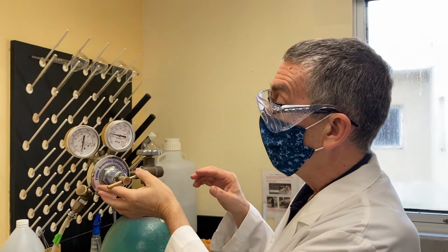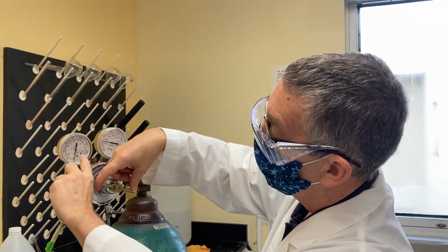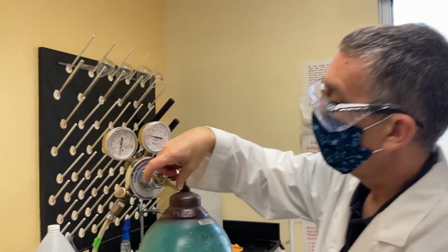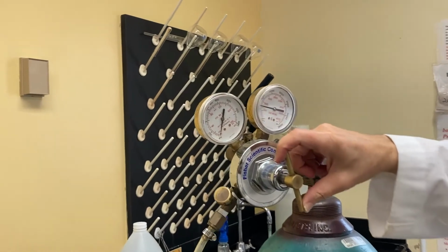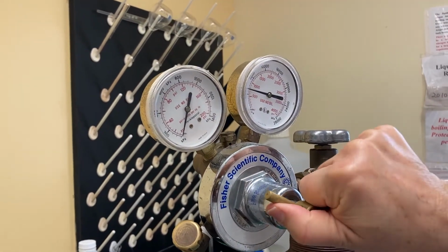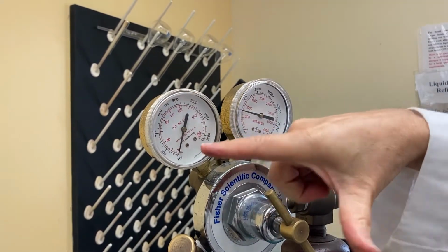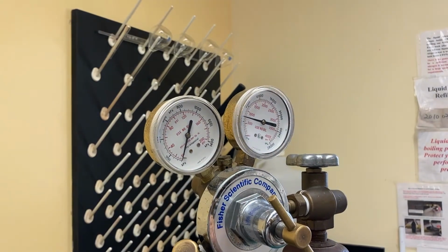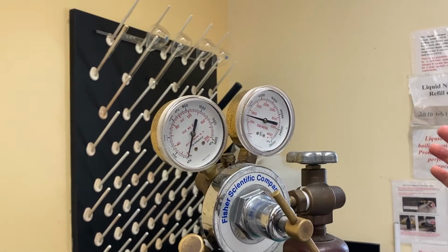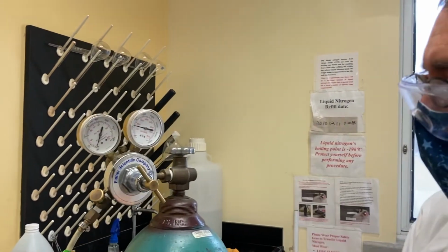But now we are opening the valve. But we can open it slowly, and you'll want to watch this left-hand pressure gauge go up. Okay, it doesn't have to move far. And if you see the scale here, we have much less pressure in the left than on the right. Okay, so don't overdo this. You can always open and add more pressure later if you need to.